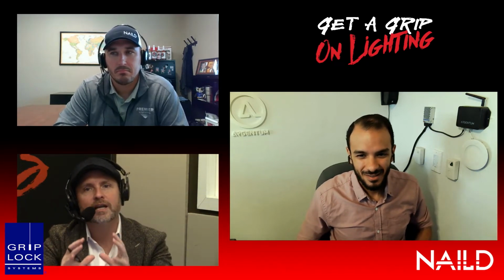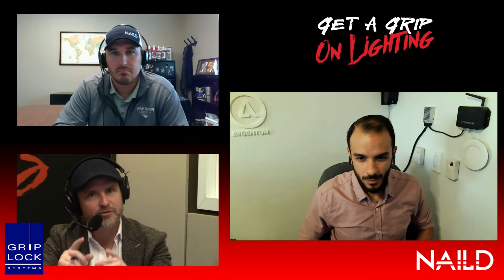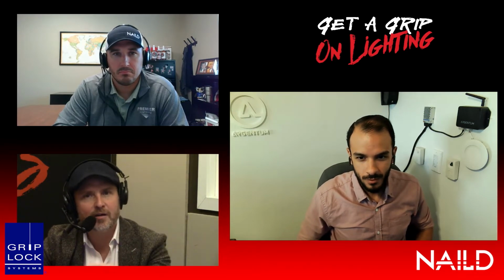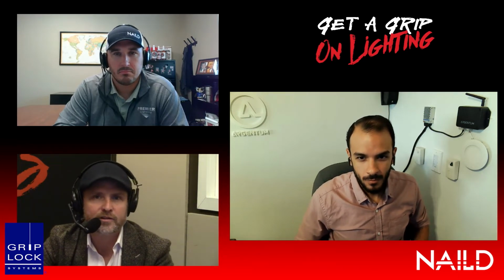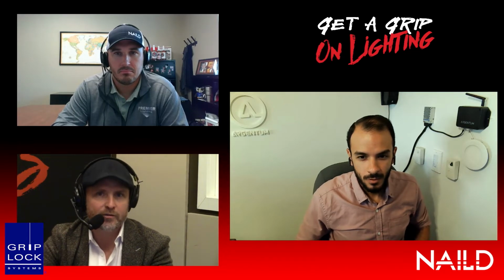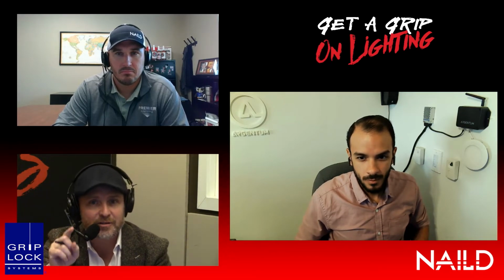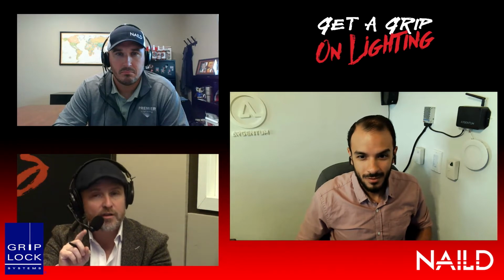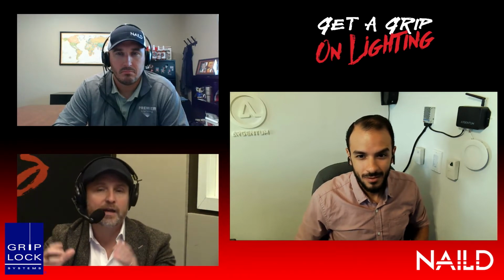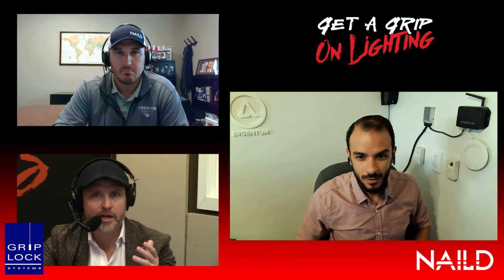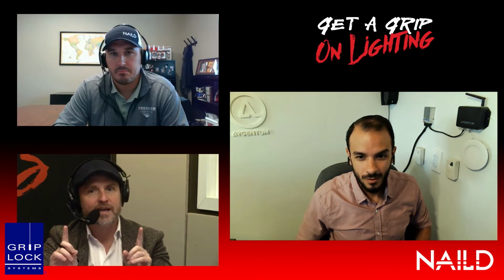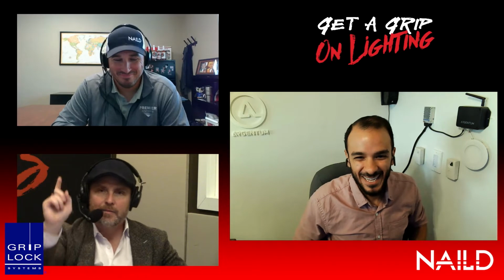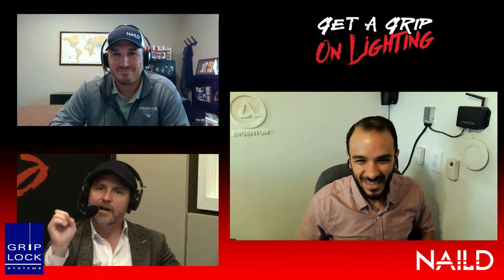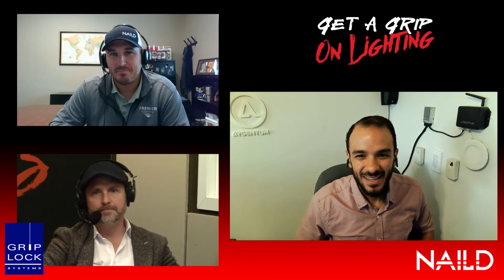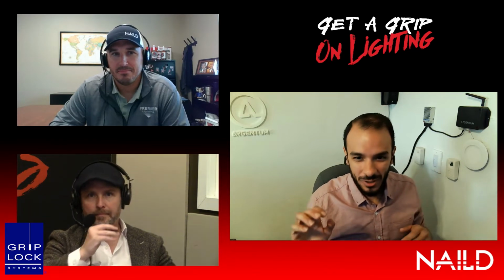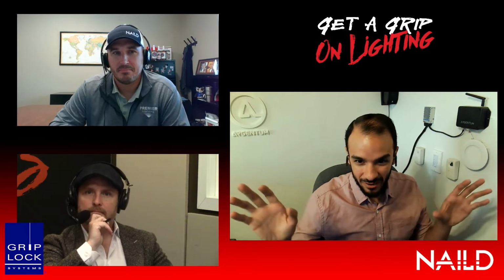You need to mechanically protect wires that are in a building for infrastructure. Don't even try to. The PoE guys tried that on me, and I said, listen, you've never installed or worked in troubleshooting electrical if you say that wires don't need mechanical protection. They need mechanical protection, not just for shock reasons, but also because we don't want to be damaging the infrastructure when we're working on the building. So don't make that case. I don't like that case because it's not good. You may be right that it may be safe to touch, but it's not safe to just have in the ceiling unprotected.